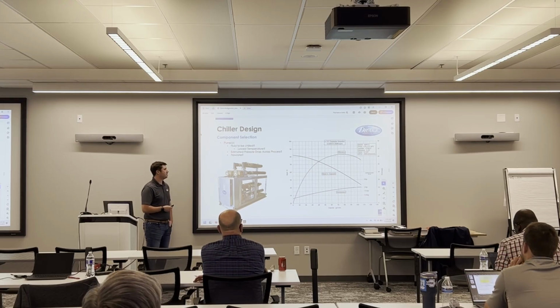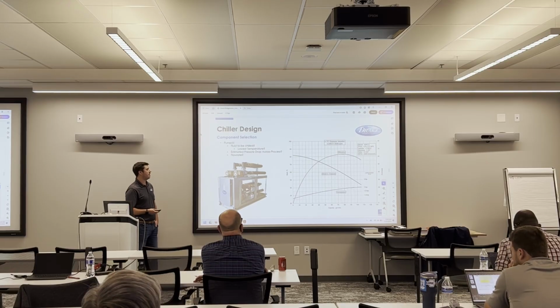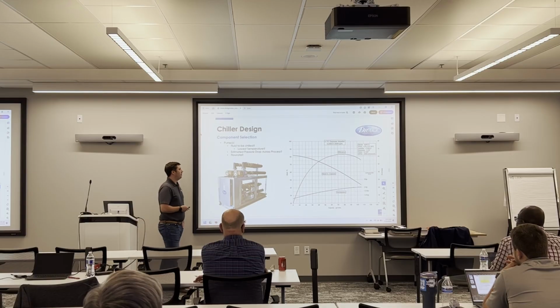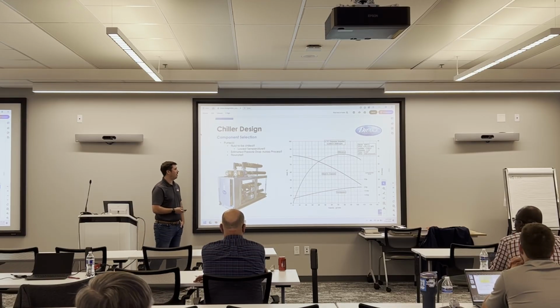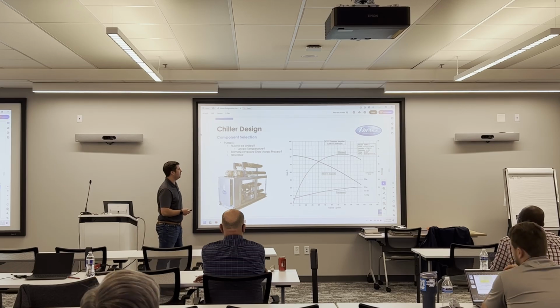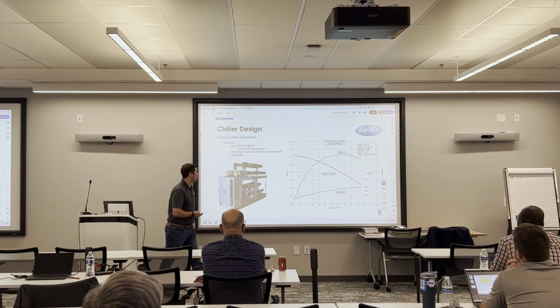I would say the pumps behind the compressor, this isn't a component you want to get wrong. You can have a chiller that's sized for the heat load, but if you don't have the pumps to deliver the fluid to the actual process loop, what's the point? On the right-hand side here, I just have an example of a pump curve. This is a curve of water. So we've got a couple different lines here, so we can kind of go through that.